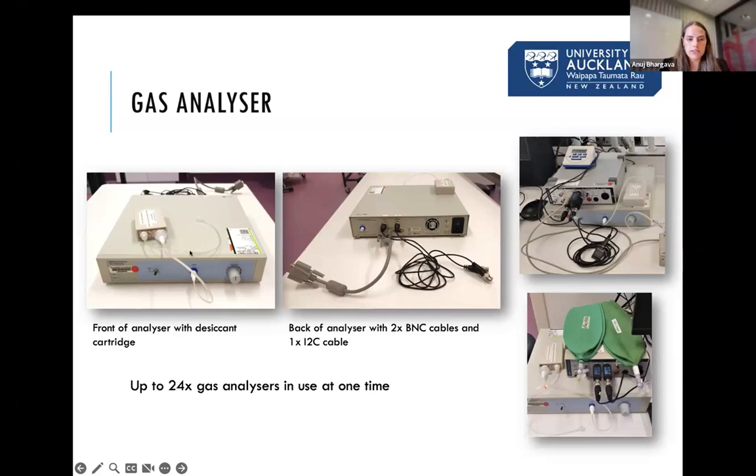So one thing we do in advance is we dry the desiccant, and because we reuse it, we will fill all the cartridges back up, and this is just more sustainable and cost effective for us.